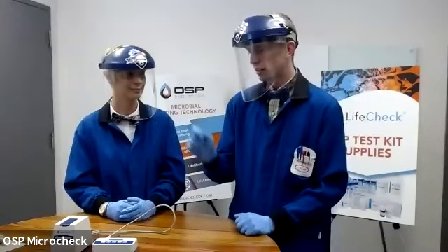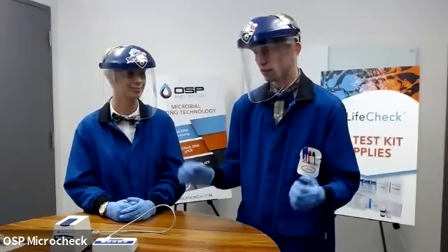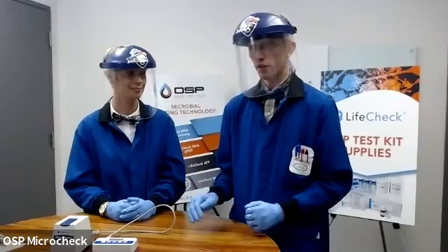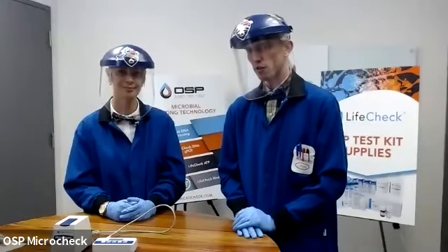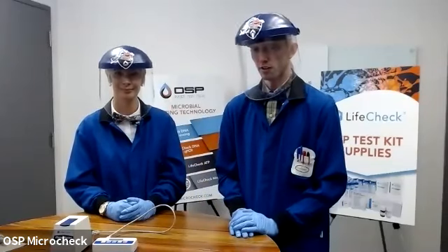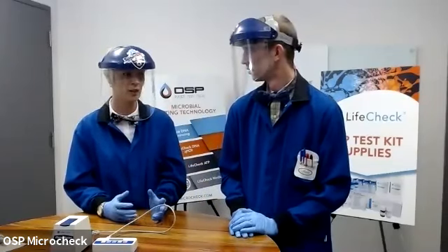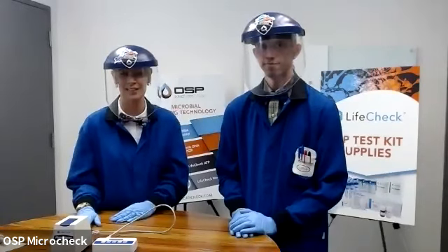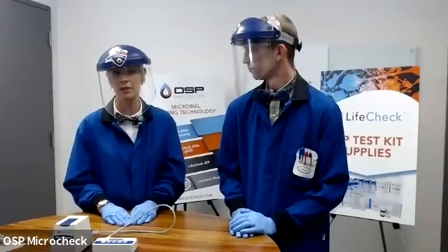So if I'm doing 10 samples and it takes me half an hour to do them all, I can be rest assured that in that time my enzyme should still be healthy. If I come back with another batch of 10 samples 2 hours later, you bet I'm doing another standard RLU test to make sure that enzyme is still healthy. And part of the reason we let you know that temperature does have an effect on this is to take a look around in your surroundings as you're doing this. If you are doing this on a really hot summer's day, and you're worried because, oops, I forgot to stick it in the cooler, I left it on the tailgate, take another reading and just be assured.